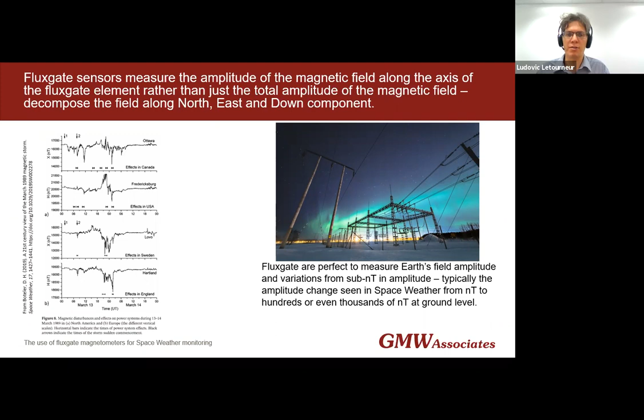So if we look in a bit more detail at the fluxgate, a fluxgate is typically a piece of high-permeability core material with an excitation winding and a pickup coil wound around it. And there are different topologies for fluxgates: ring core, single linear cores, or twin linear cores. I'll talk a bit more about the twin linear cores, which is the type of sensors used by Bartington. So if we look at the left-hand side, typically you have two pieces of high-permeability core material with an excitation winding around each of them. The windings are in opposite directions, so that when we apply our excitation signal, one core reaches saturation in a positive manner and the other one will be negative. And then around that, we have a pickup coil.